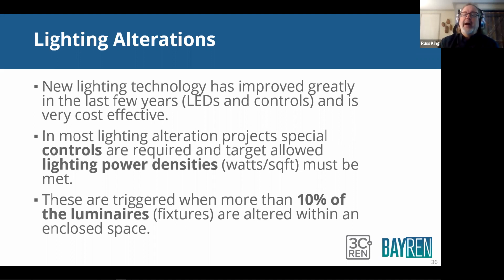What triggers these requirements? How much of a change is required to trigger these requirements? The magic number is 10% of luminaires or fixtures within an enclosed space. So you've got an enclosed space, a room, or a retail space or something like that. If you're replacing more than 10% of the fixtures, it triggers these requirements, okay? In a small space, if you've got less than 10 fixtures in a room and you replace one of those, that's more than 10%. So it's gonna trigger this requirement. So 10% is not a whole lot, all right? All right, so 10% of fixtures within an enclosed space is the magic number.